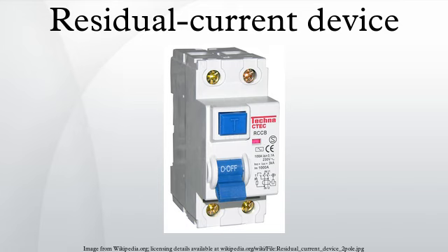United Kingdom. The previous 16th edition of the IEE electrical wiring regulations required use of RCDs for socket outlets that were liable to be used by outdoor appliances. Normal practice in domestic installations was to use a single RCD to cover all the circuits requiring RCD protection but to have some circuits not RCD protected. This was to avoid a potentially dangerous loss of lighting should the RCD trip. Protection arrangements for other circuits varied.